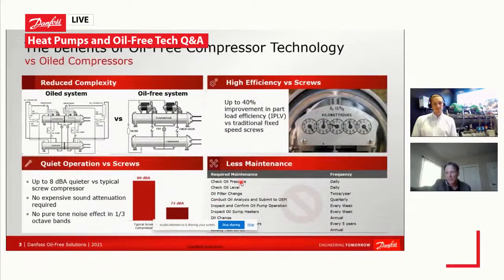But specifically what you see with those units is that they're about 8 dB quieter than an equivalent capacity screw compressor, because the two primary noise generators coming out of a HVAC system, whether it's a chiller or a heat pump or a rooftop unit or whatever, the primary noise generator is the compressors, and the primary noise generator coming from the compressors is the metal-to-metal contact. If you go oil-free, then the best way to do that is with no metal-to-metal contact, and the byproduct of that is the extremely low sound. And all of that going oil-free also results in a compressor design and a system design that is extremely low maintenance, which also improves the overall life cycle cost performance of a Turbocor based unit.